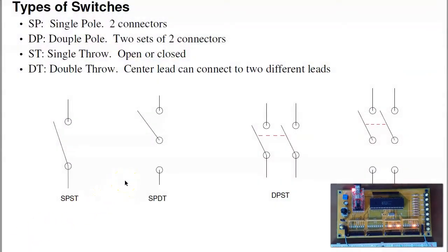Now there's a couple different types of switches. There's single-pole, double-throw, or single-pole, double-pole, single-throw, double-throw. A single-pole, single-throw switch are like these push buttons. It's either open or closed. A single-pole, double-throw is, I want, say, may have a motor go forward or reverse. I have two different directions for it to go. A double-pole, single-throw is actually two switches tied together.